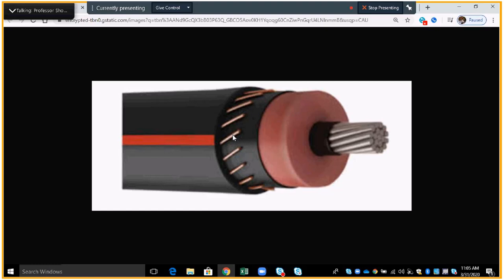And the outside right here is the outer jacket. Red stripe right here designates that it's a power cable. So, from the inside: conductor, conductor shield, insulation, semiconductor, neutral ground, outer jacket.